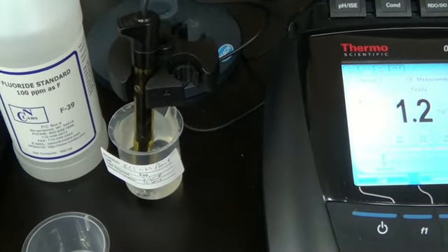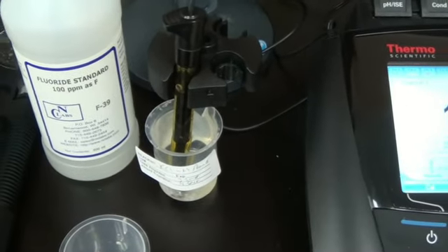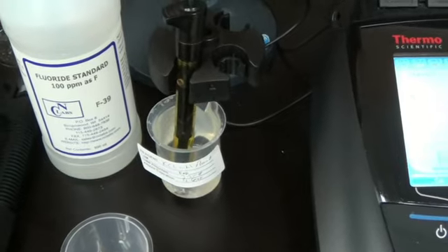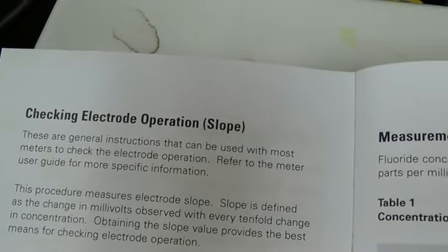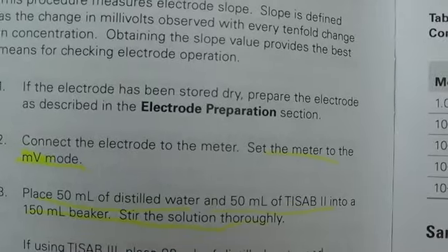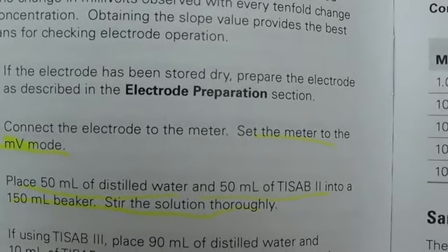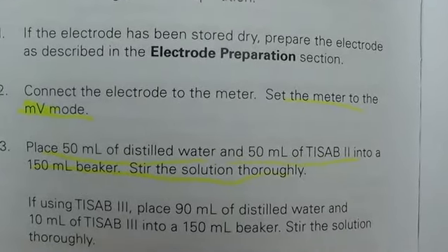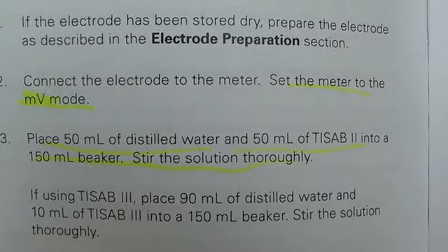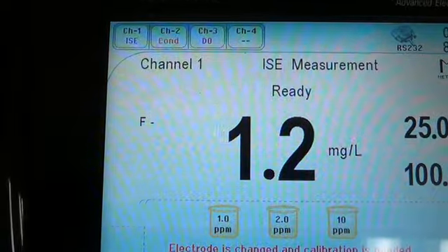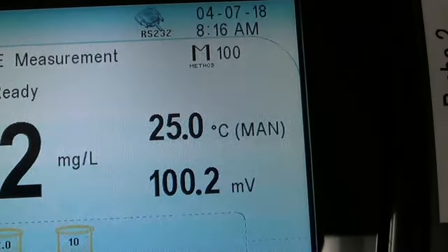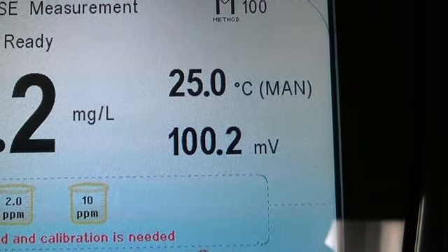Next thing you have to do is check to make sure your probe is working properly. To do that, you must check the slope. So find that page in your book, checking electrode operation slope. And here are the directions. We have already put the electrode onto the meter. Next we have to set the meter to the millivolt mode. It is right now set up for fluoride, but it does have millivolts here, so we're going to check that out right there.